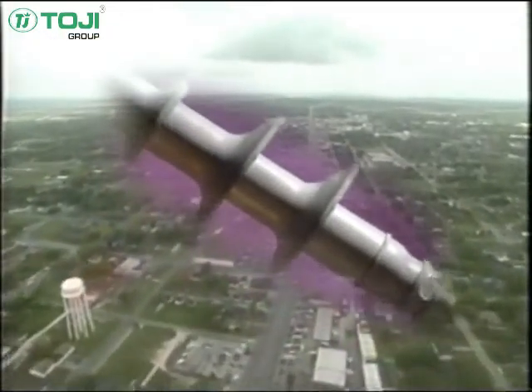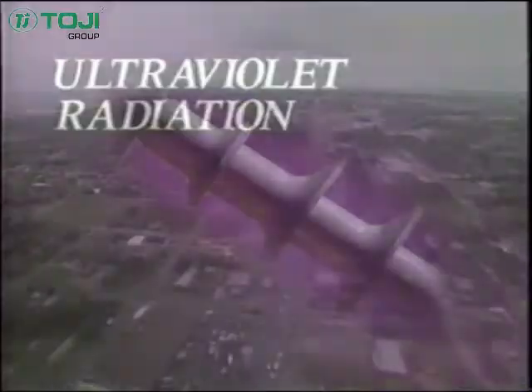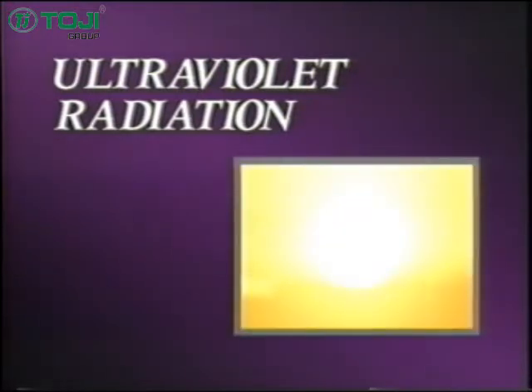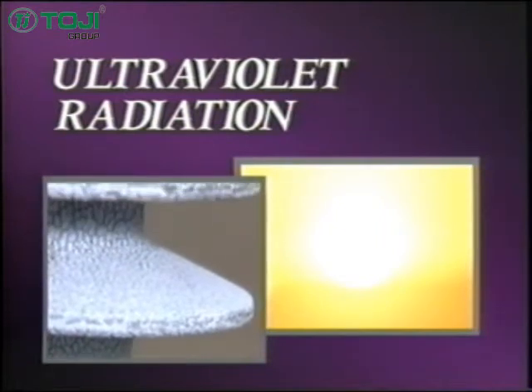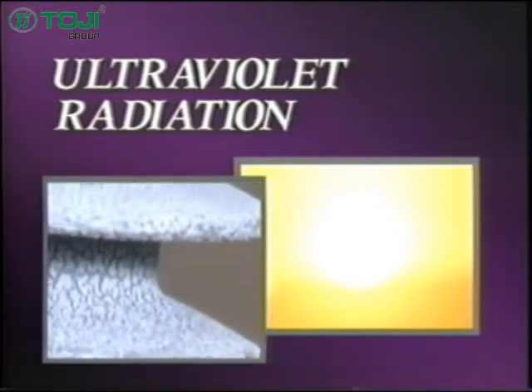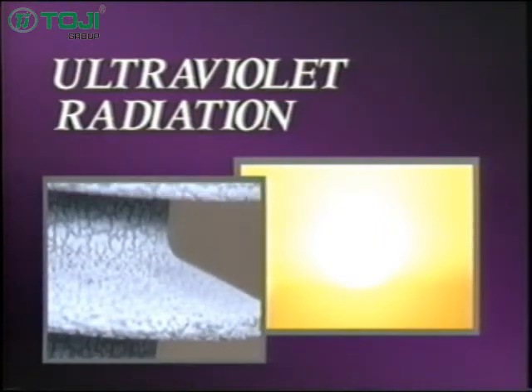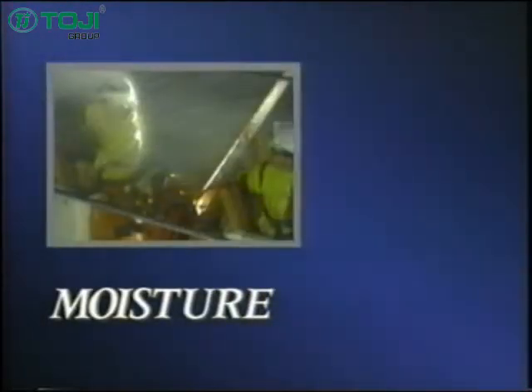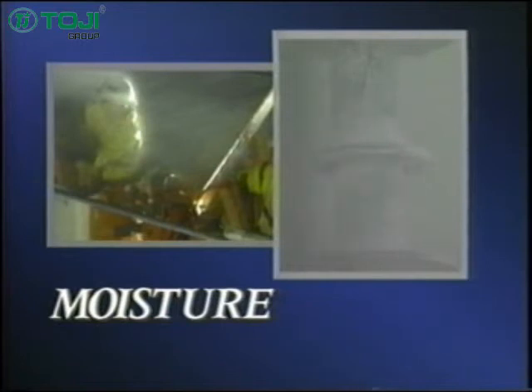Besides the aging process of the polymeric material, the surface is affected by three main environmental factors. One is the amount of ultraviolet radiation the surface receives. Sunlight causes the crazing and cracking of the surface, which in turn leads to greater absorption of moisture and contamination. The second is moisture. Wetting the surface of the insulator decreases the surface resistance, thus increasing the amount of leakage current.